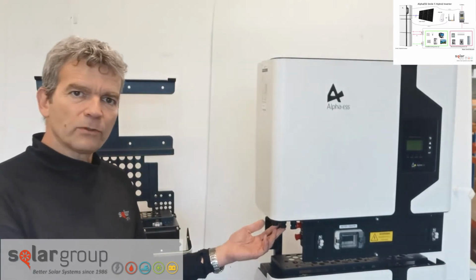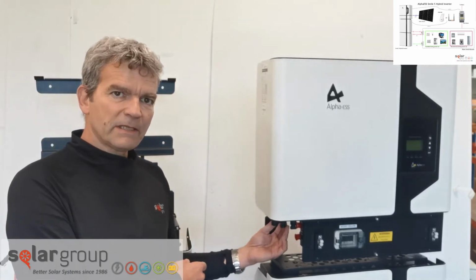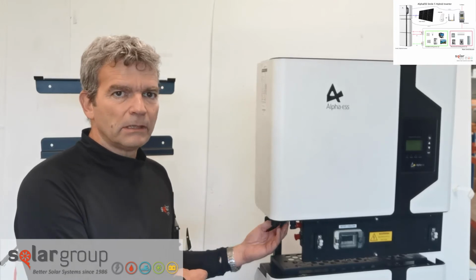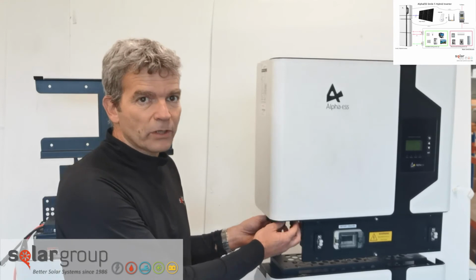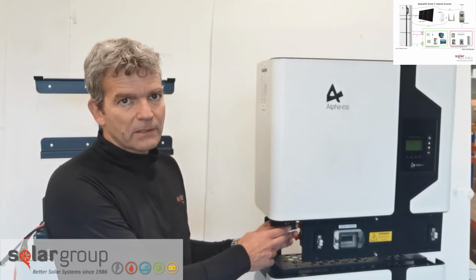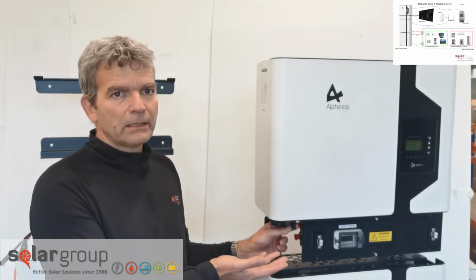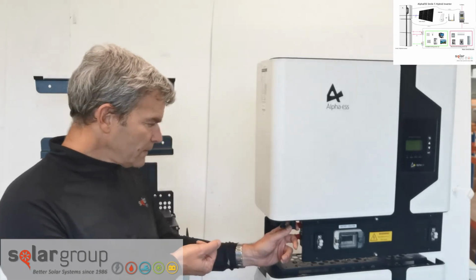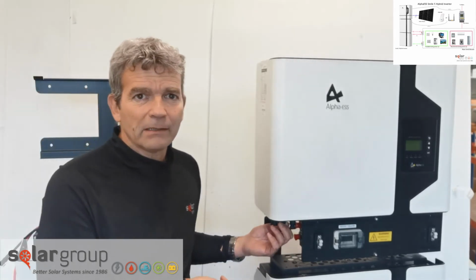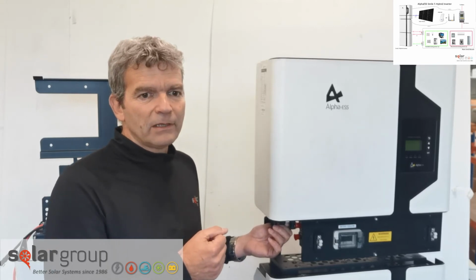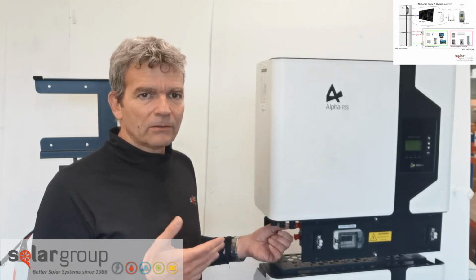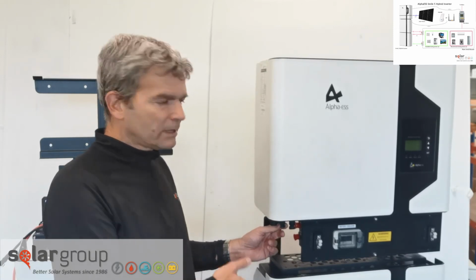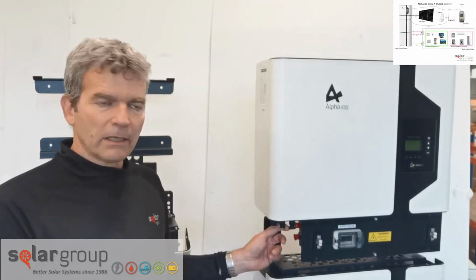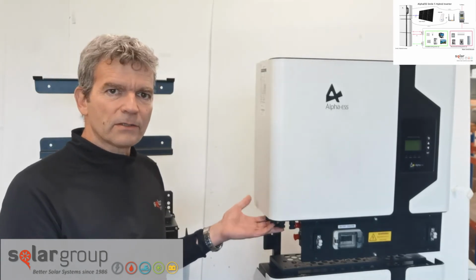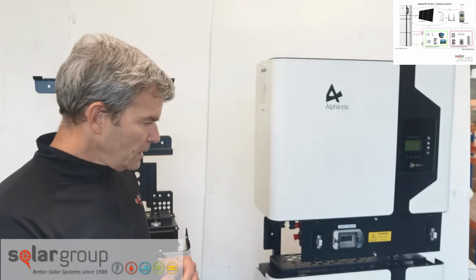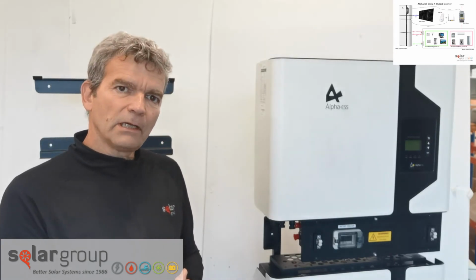Next one is DC connection to the solar panels. There are two MC4 connectors here. They need to go to a maximum of 3.3 kilowatt per string, so you can do two strings. 15 amps is also the maximum current, and obviously open voltage, you can't do more than 600 volts. And basically the minimum amount of panels, I would say, 5. If you're talking about 60 cells, you need to have a good 200 volts DC to get this inverter waking up easily and work efficiently. So there's not much to talk about the DC, just two strings, 3.3 kilowatt each. As far as the cabling, that's pretty much it.